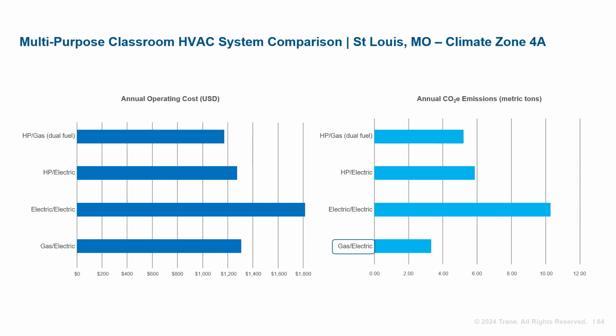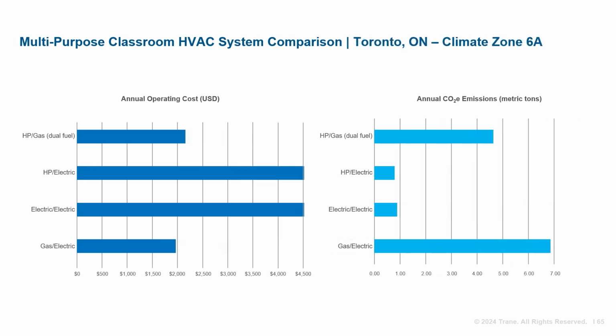However, if the goal is to save annual operating costs, a heat pump with auxiliary natural gas heat has the lowest annual operating costs. Lastly, let's visit our friends up north in Toronto, Ontario. Obviously, the winter design in Toronto is the coldest of the cities analyzed and offers the most hours of heating operation.